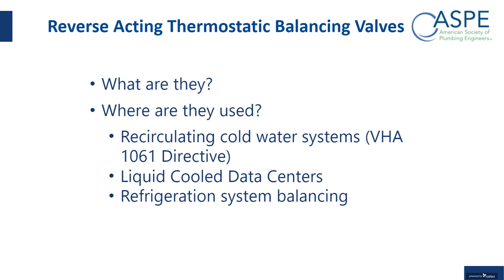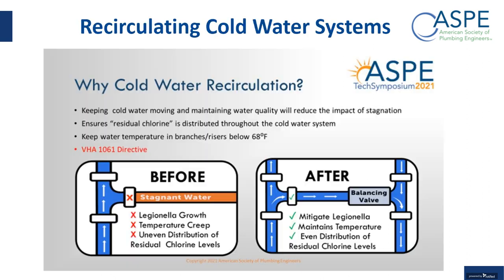VHA in their 1061 directive strongly recommends recirculating the cold water. There's a number of systems out there now that are recirculating cold water in VA hospitals. It's also a great application for liquid-cooled data centers, balancing liquid-cooled data centers, and then refrigeration system balancing. So I'll go over those examples real quick. Cold water recirculation.